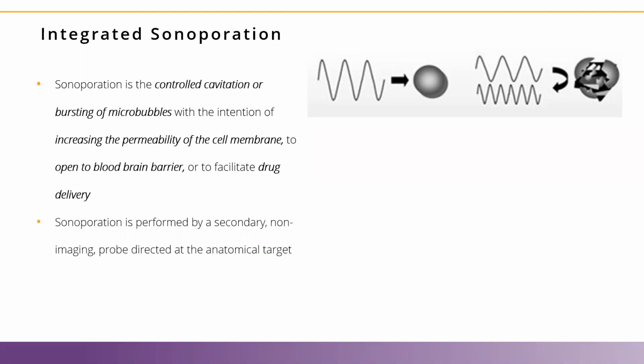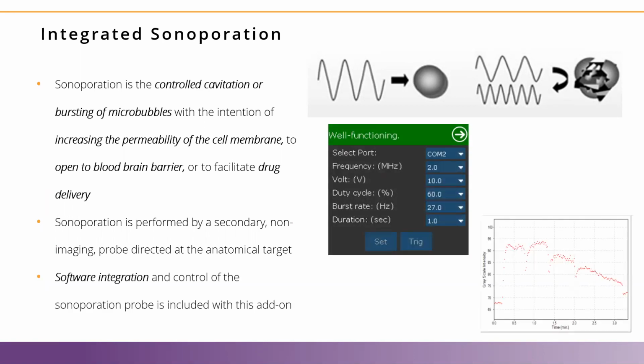So the sonoporation probe is a secondary probe. It's a non-imaging probe, which is angled towards the tissue of interest. That probe is integrated within the software of the Prospect T1. From there, we can control when it fires, how much energy it fires with, and many of the different settings which would be desirable to control the sonoporation event.